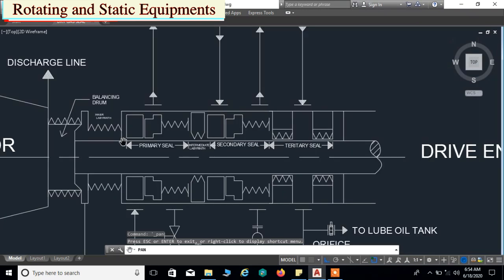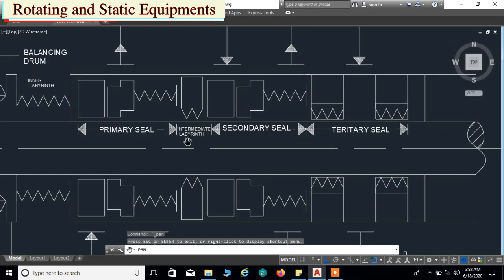Next to the inner labyrinth, the dry gas seal unit is started. This is called a double mechanical gas seal arrangement. The first unit is called the primary seal. It consists of a set of seal ring, mating ring, primary sleeve, primary housing, primary retainer, primary static elements, and springs.